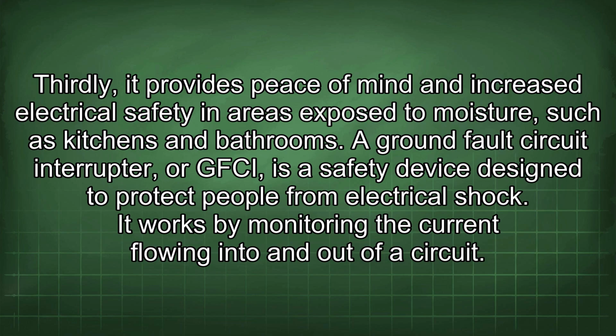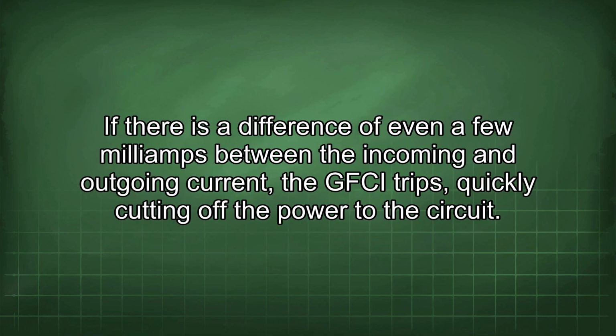A ground fault circuit interrupter, or GFCI, is a safety device designed to protect people from electrical shock. It works by monitoring the current flowing into and out of a circuit. If there is a difference of even a few milliamps between the incoming and outgoing current, the GFCI trips, quickly cutting off the power to the circuit.